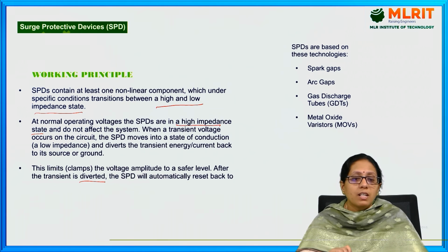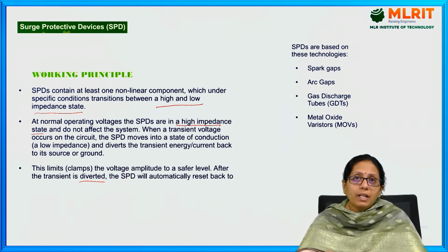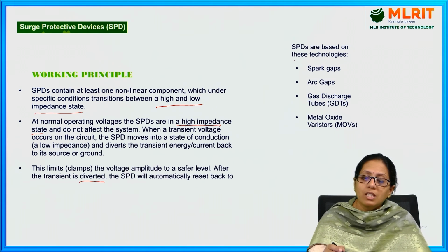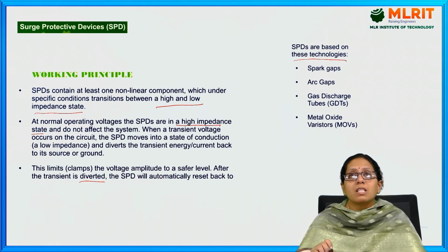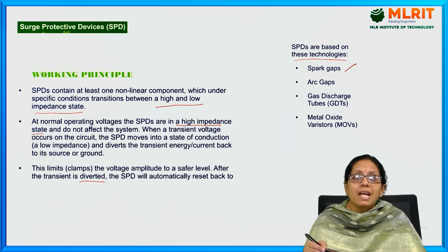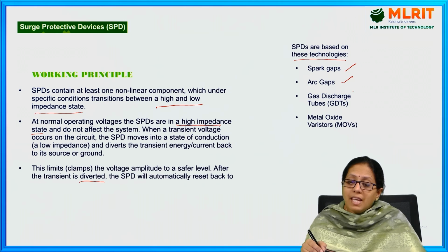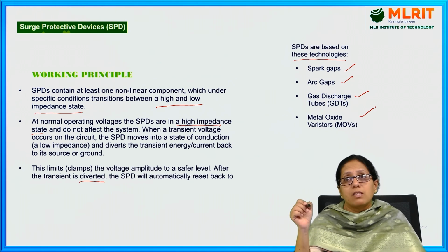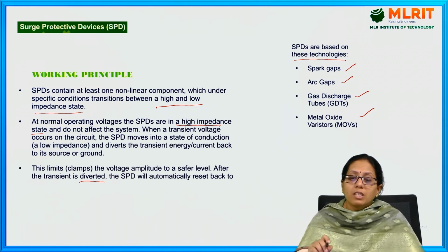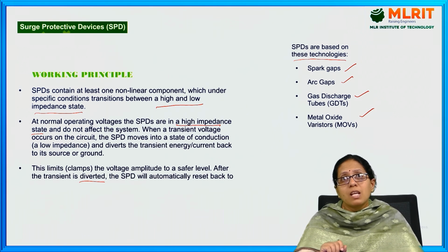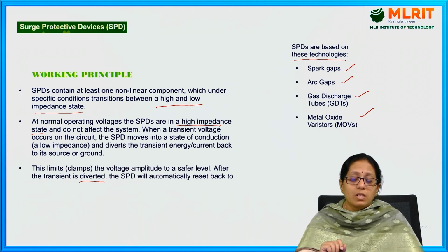being diverted, the SPD will automatically reset back. The SPD is based on these technologies, that is spark gaps, Arc Gaps, gas discharge tube and metal oxide varistors. Based on these different technologies, the SPD works.